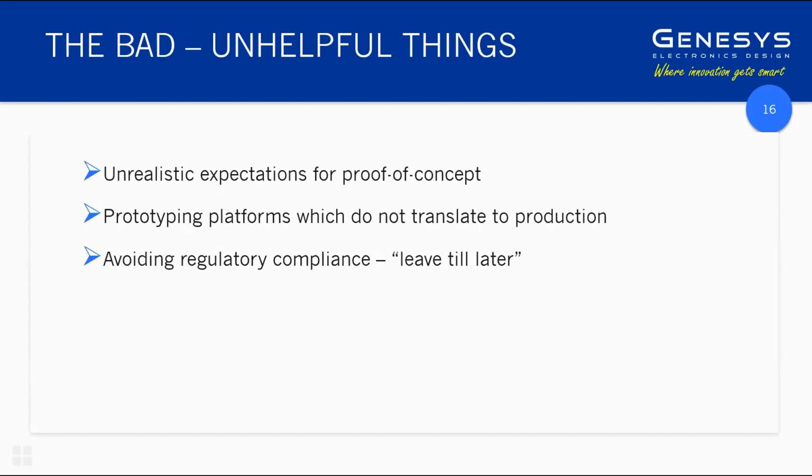We've talked a little bit already about the unrealistic expectations of proof of concept. A lot of people develop something on their own using what we call single board computers, like Raspberry Pi or Arduino. Generally speaking, they cannot be used at all in developing a medical device.